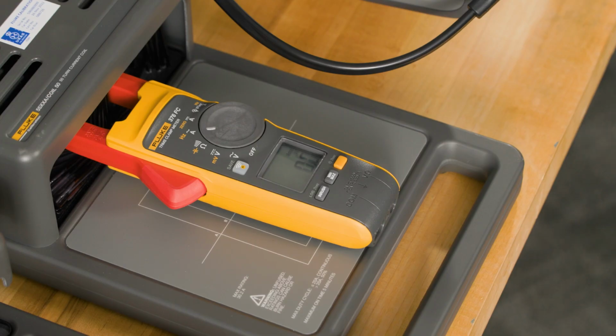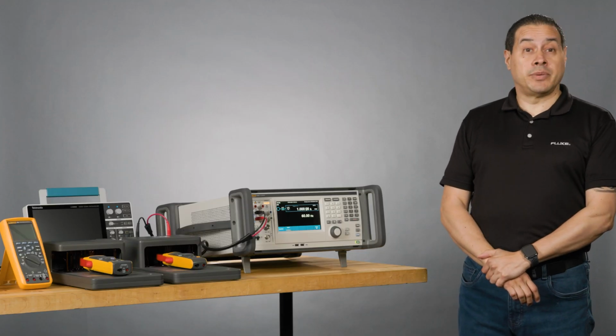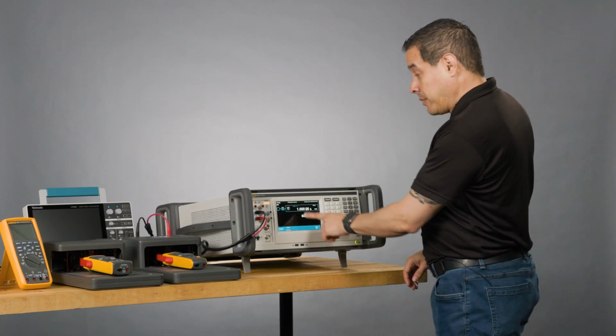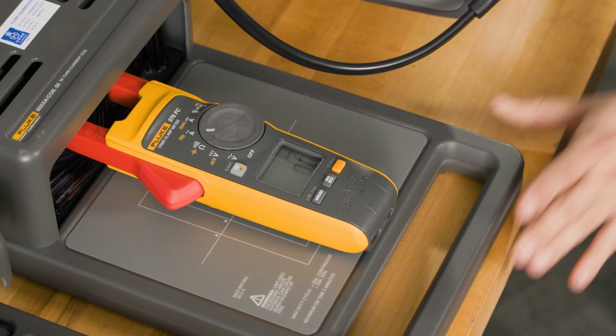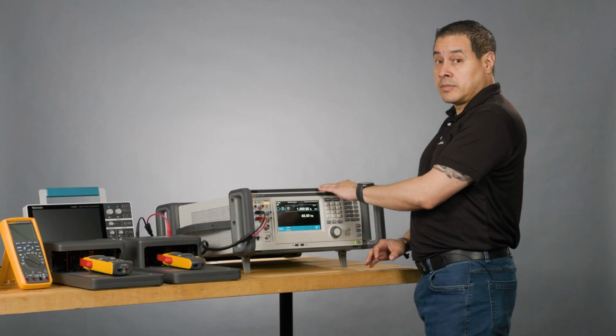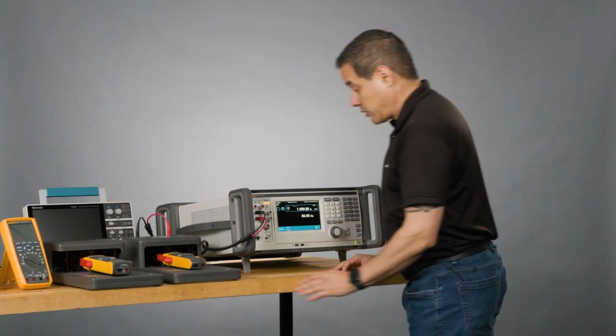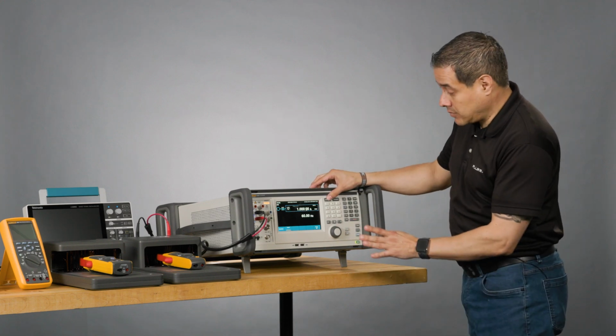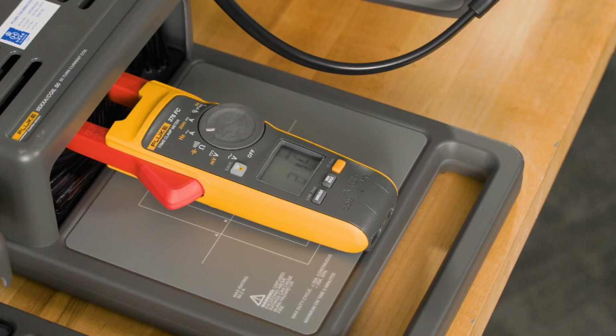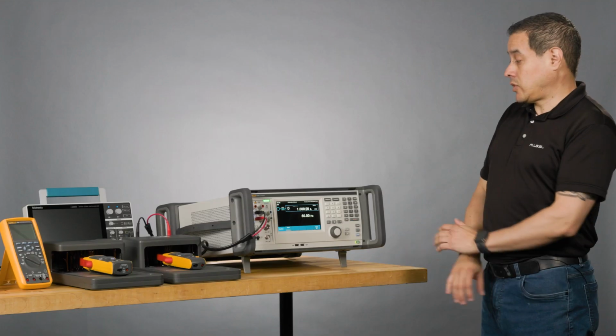Now I'm going to show you how to calibrate clamps in AC current. In this case, I'm going to use 1 amp for starting. So 1 amp, I'm using a 50 turn coil, so everything that goes out from here gets multiplied by 50. So 1 amp, 60 hertz, looks good. Operate. Then I'm reading 50.4, which is fine. Stopping.